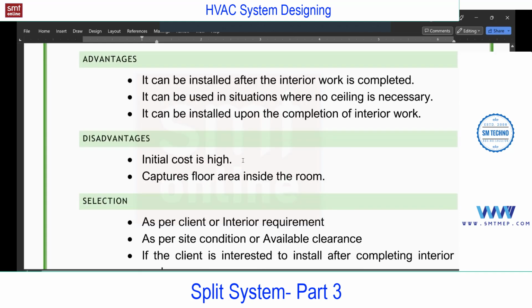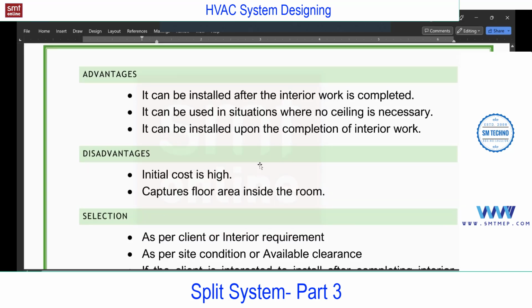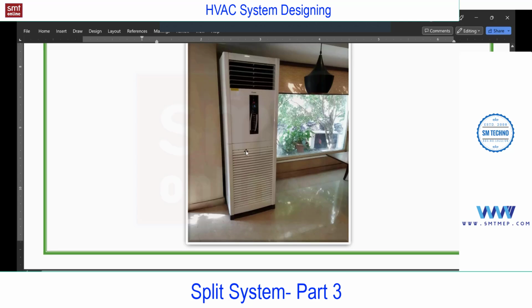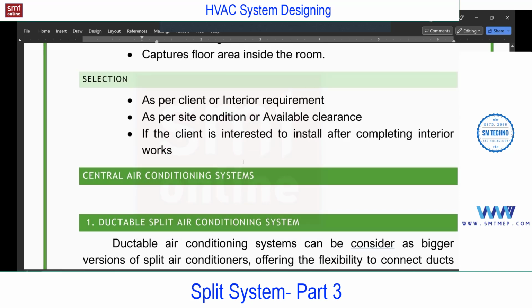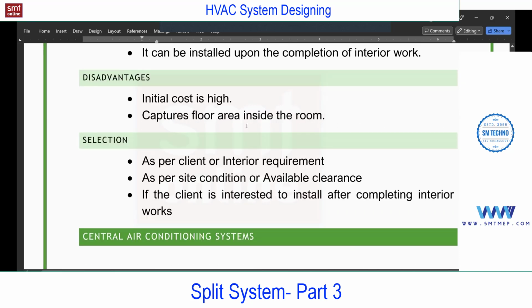Now, if you talk about disadvantages, even compared with the cassette, the cost is high for this, because you will find a tall body unit, so the metal cost and all this. So from a costing point of view it is almost 40 to 50% higher compared with the high wall. If you get a 1.5 TR high wall for 50,000, for this one you need to spend 70 or 80,000, because this is not commonly available either. So from a cost point of view, also, it will capture the floor area.